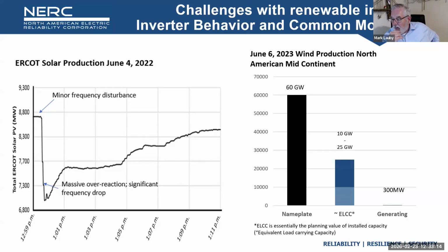I mentioned this one already, the 60 gigawatts that was generating on the order of 300 megawatts. If you use effective load carrying capability or some of the other measures, you'll miss it. So you need to do hour-by-hour analysis and look at different scenarios now. It's much more scenario planning than working just for the peak. It used to be that if you can handle a peak, you can handle anything else, even peak on the shoulders. That no longer holds. You need to really do the detailed analysis.